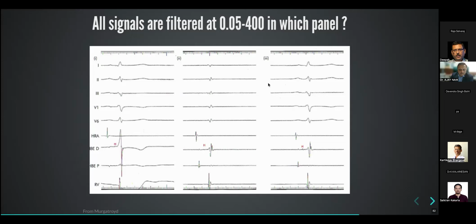So these are the usual settings. For an ECG, you go 0.05 to about 500, whereas for the intracardiacs, you start at 30. Now, if for the intracardiacs you also use 0.05, you'll see these low frequency signals in the bipolar, which you don't want. You don't want these far field repolarization signals. So the intracardiac has to be filtered at 30. But if you filter the ECG at 30, you can see how the P waves and T waves disappear. So the ECG has to be at 0.05. It's a very good illustration of why you need this kind of differential setup for the ECG and the bipolar signals.